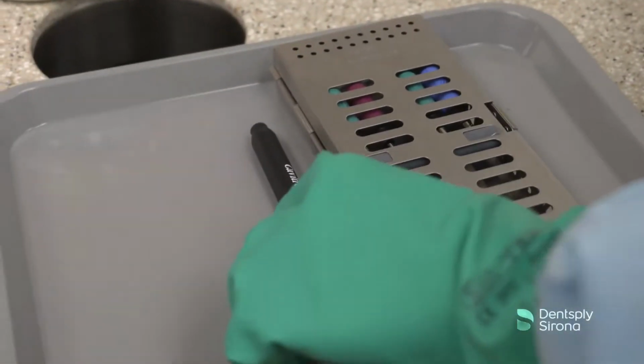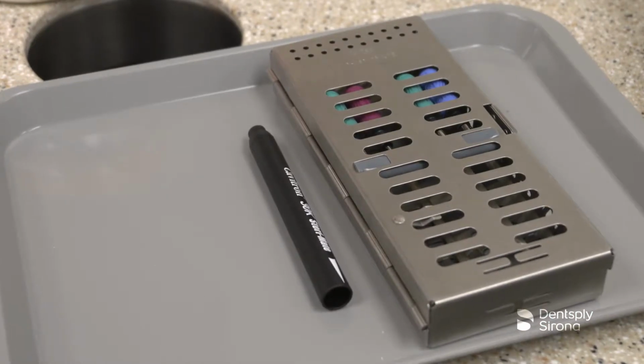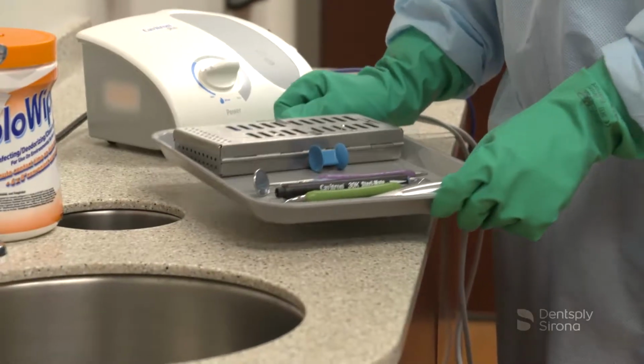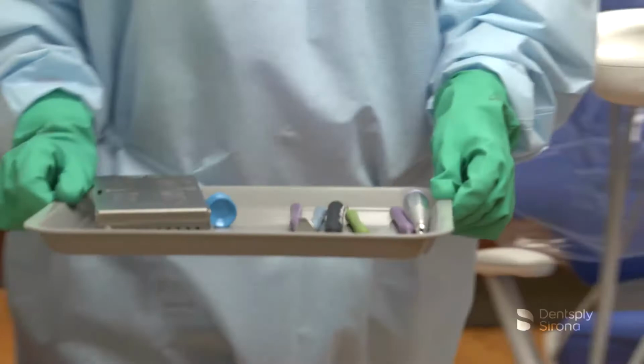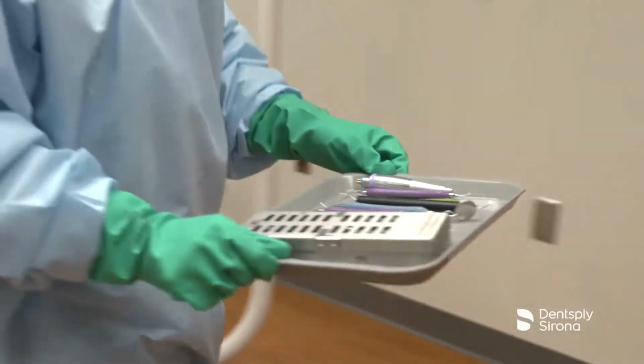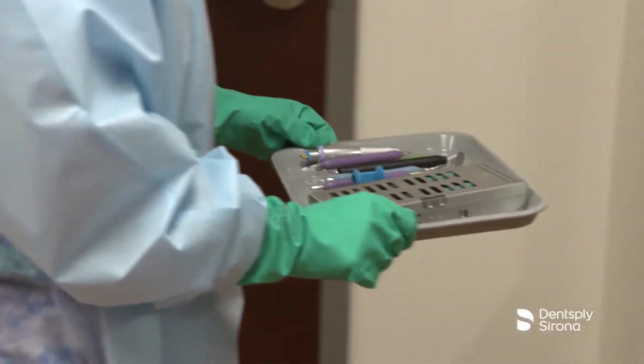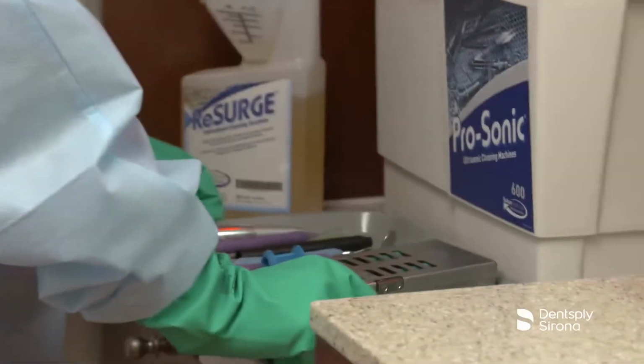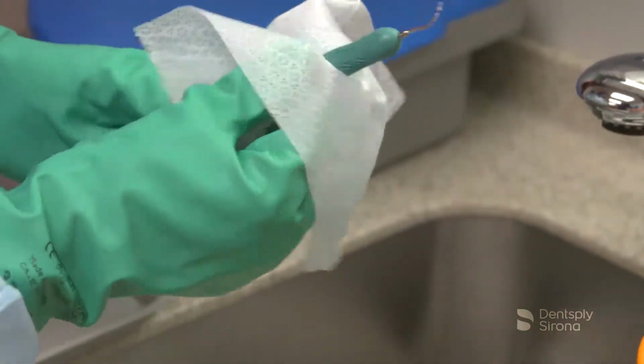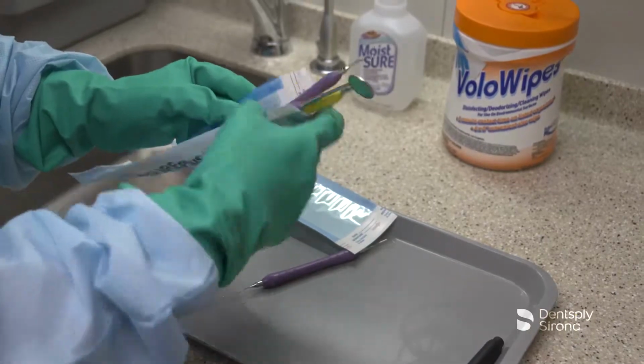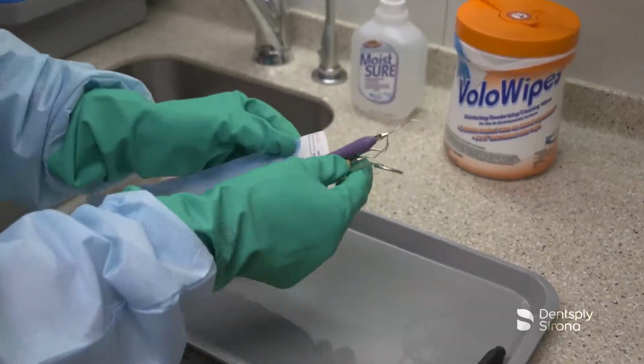Contaminated instruments should be transported in instrument cassettes, trays with sides, or labeled containers with lids when cassettes are not an option. Occupational safety must be followed by clinicians to reduce the risk of sharps injuries and exposure to contaminated instruments. Instrument reprocessing plays an integral part in routine infection control procedures. Used instruments can harbor bacteria and bioburden and should be transported to the reprocessing area immediately after their use.